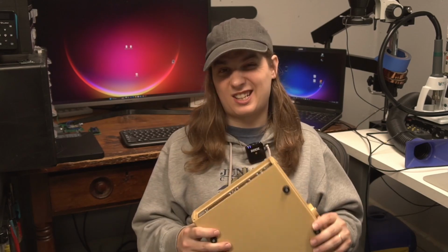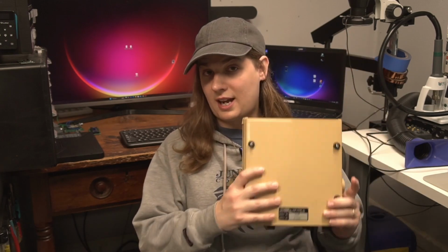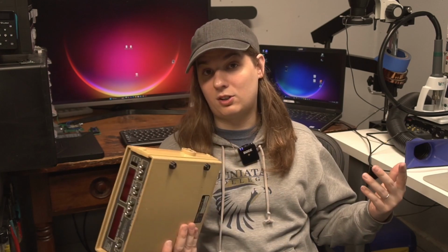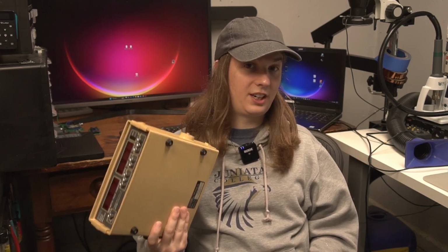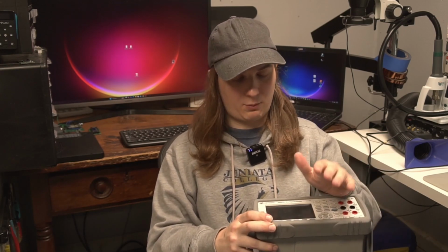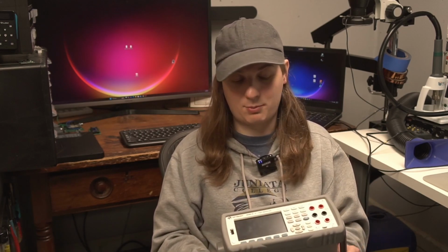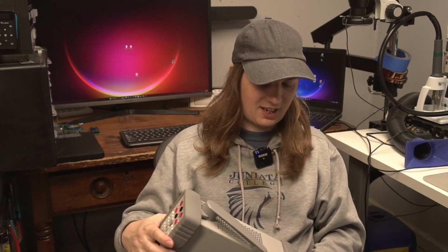That way, for anyone that's kind of thinking about repairing their own test equipment, getting their lab set up with repaired test equipment, you get an idea how this process goes. You can follow along in the old video, which I should have down in the description, on how we fix this thing, and then we can follow along on how to get it where it gives you at least a halfway decent measurement. Because like I said, this thing's way off right now, so we're going to get it as close as we can. We'll be using our Keysight to calibrate it, so it's a pretty accurate measurement that we get off of this. It has been 2 years since this was calibrated, and I also repaired it. So definitely, this guy's out of cal, so it's not a valid calibration, but it's good enough for what we do here in the lab.